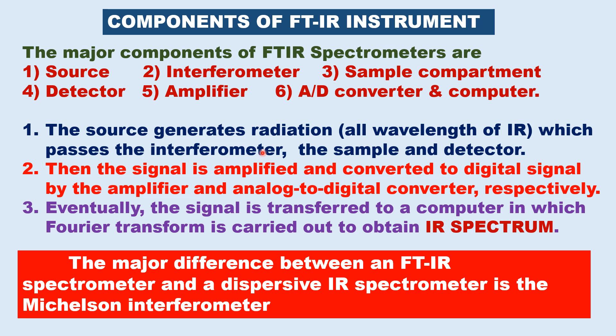The instrument also includes an amplifier, analog-to-digital converter, and computer. In the animation, only one wavelength was shown for simplicity, whereas in an actual experiment, IR radiation of all wavelengths in the IR region passes through the interferometer, then the sample and detector. The signal is amplified and converted from analog to digital. Finally, the signal is transferred to a computer where Fourier transform is carried out to produce the IR spectrum.